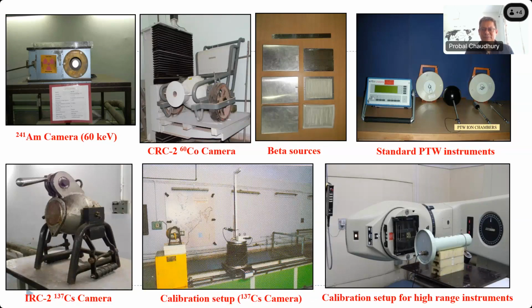These are photographs of the equipment, calibration facilities and calibration setups available in the lab. Some of you who may be interested in visiting can then have a better look. These are only photographs, and this one is a calibration setup for high range instruments. The instrument being calibrated here is from the Indian environmental radiation monitoring network. These are solar powered standalone radiation monitors. Around 550 of them are being installed at various locations in the country to continuously monitor the ambient radiation level. They have different ranges of detectors, and to calibrate high range detectors we require this type of facility. This is one example of how calibration is carried out.